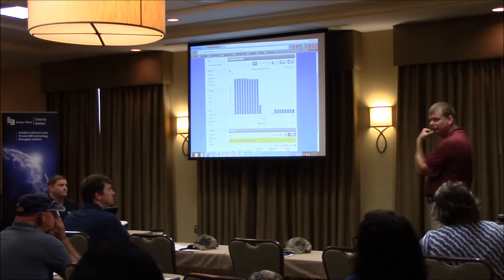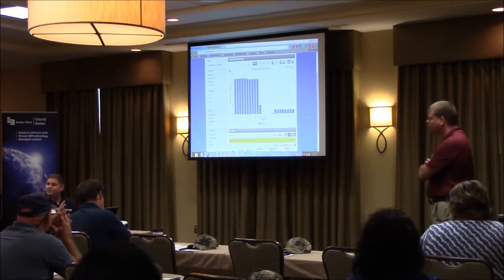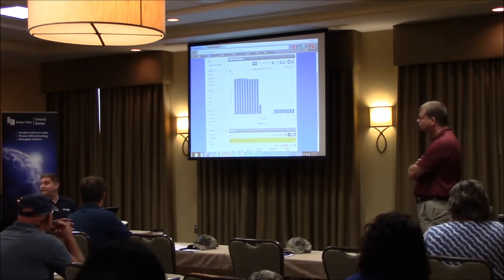And then we were also able to see the same quantity on the master meter at the town that serves this sewer plant. One of the things I was looking at is whether it was a malfunction of the meter. It's kind of an unusual situation. Our wastewater treatment plant is actually located in the town of East Spencer, so we sell the town water, and then they sell it back to us for the sewer plant. So the first thing I did was compare their master meter. Did it have the same data that I was seeing here? And it matched up.